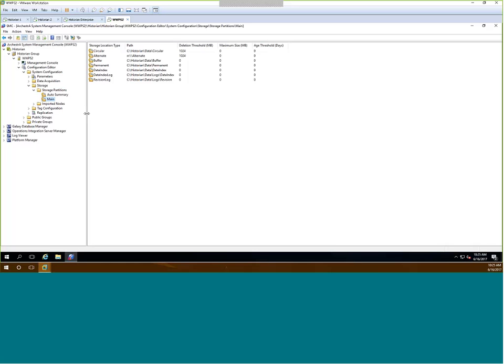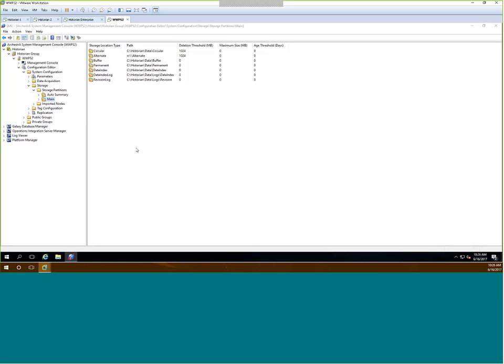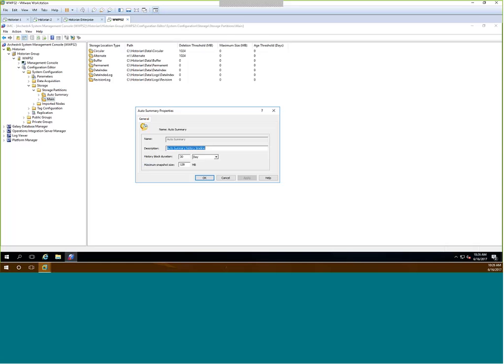If you've seen the video, you've probably saw the retrieval on our Historian and saw that we can do a year's worth of data retrieval within less than a second. So this is the reason why we're able to do that. So now within the storage partition, this is the old way for the 2014, we do a history block of 24 hours to store the data, and that's the standard. That's still there. But now what Wonderware has done is we've also added a 30-day history block to do a summary history of the data.